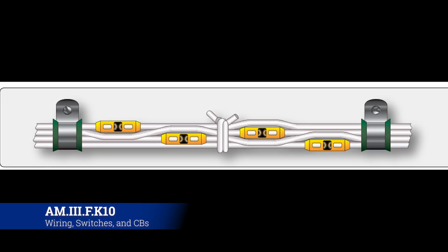Here's another one I'm pretty passionate about: staggering your splices. A lot of times you'll end up having to splice a wire run, for whatever reason, damage, it doesn't matter. The temptation becomes to basically cut the one wire bundle off straight in one spot, and then take the adjoining one and just start putting splices together. That is the wrong answer, because what ends up happening is you'll peanut butter tape over the top trying to protect the splices, and you'll end up with this big ball in the middle of the wire run that makes things more difficult.